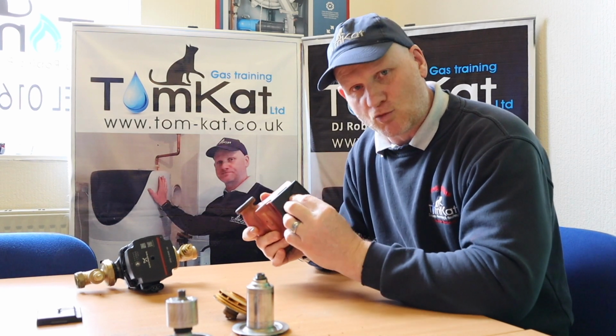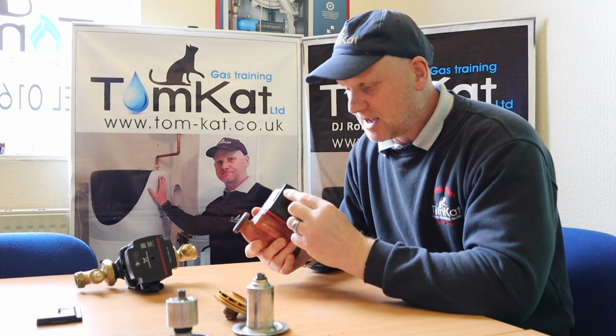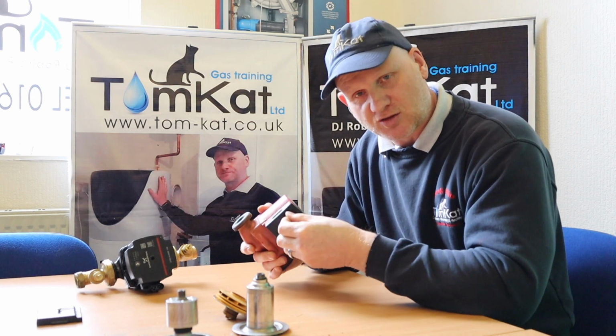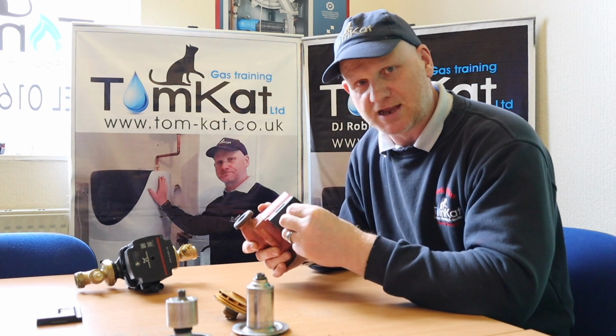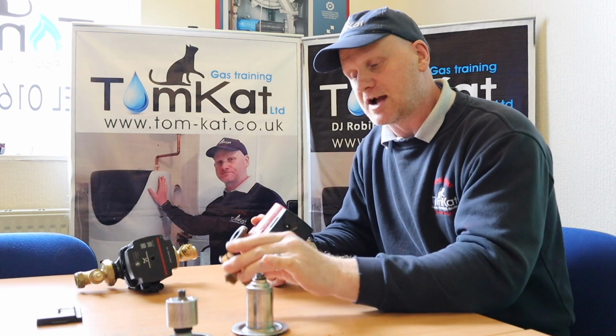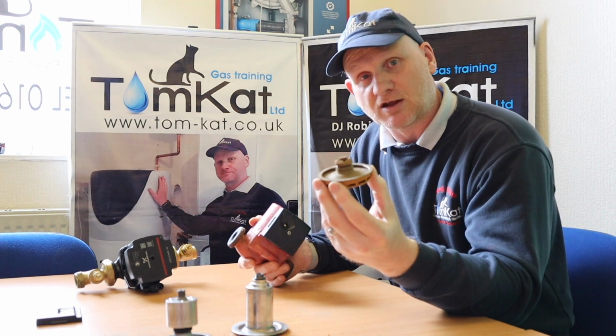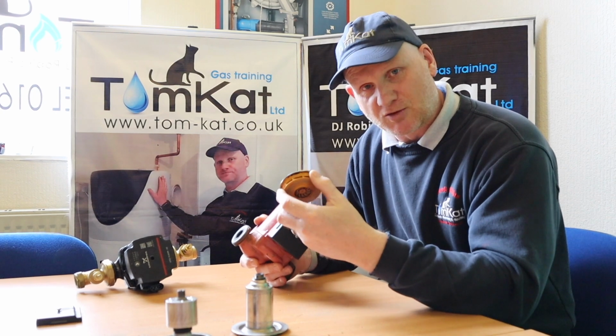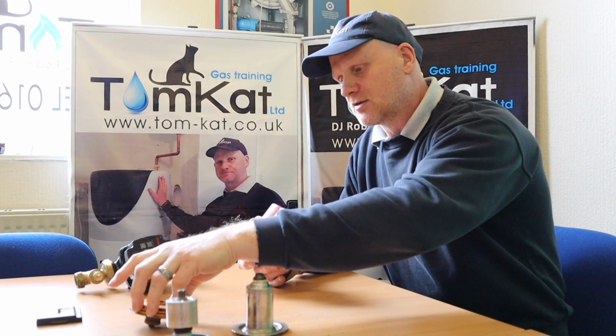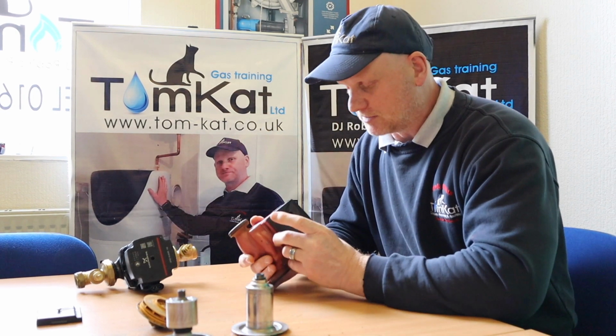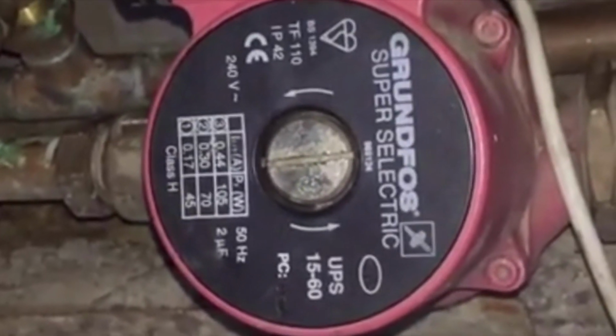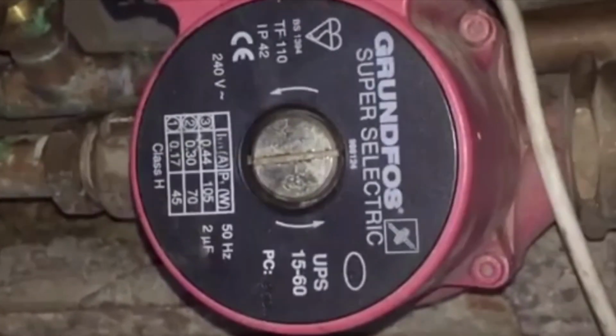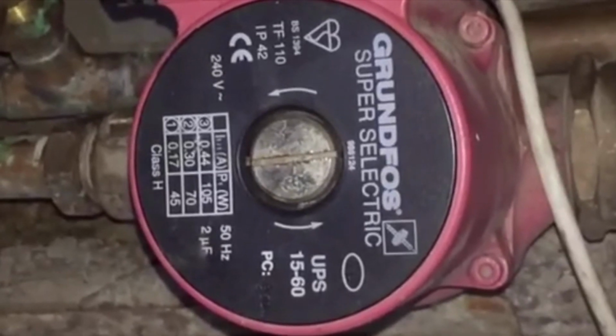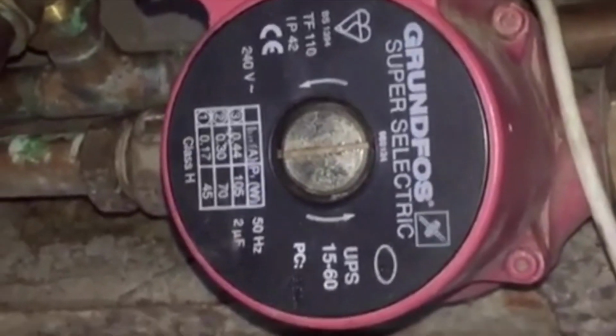Now, another thing is if you go to your pump and you hear it rattling, really rattling, and you turn the selector switch up and you can hear it really making a clunking noise, a lot of the time what that is, the impeller's fell off. So that's the impeller rattling around on the inside. So that's another common fault we've got. If you hear this noise, this is the bearings are dry, so that means the pumps have probably been installed wrong and the pump is full of air, so the bearings have dried out.